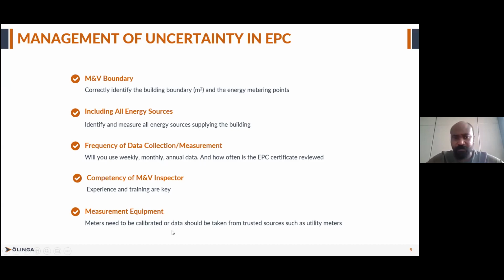a calibrated meter. Within measurement and verification, we also have this concept of traceability. Traceability again is part of good quality management system. I'm not saying it's mandated by SANAS here. What I'm saying is having traceability of your calibration certificates, knowing where they came from, knowing where the data came from, knowing the accuracy of that data is important.